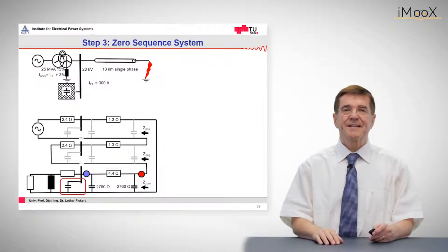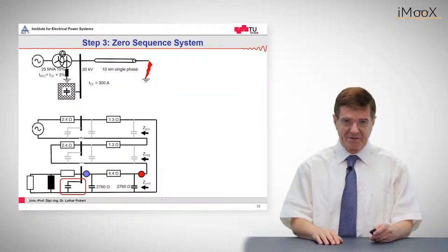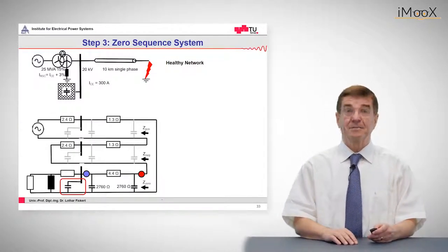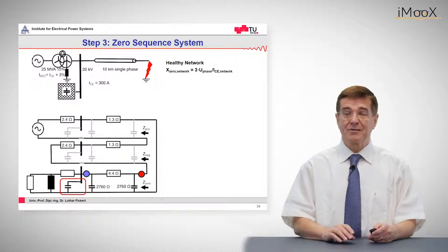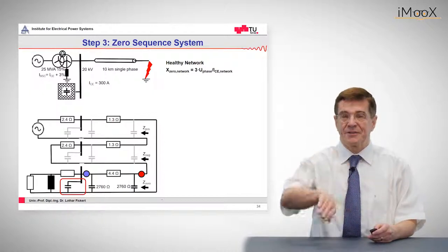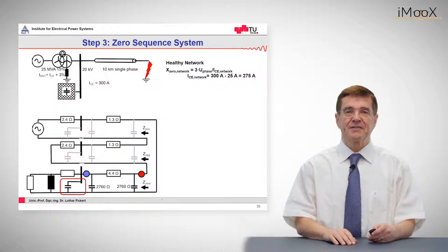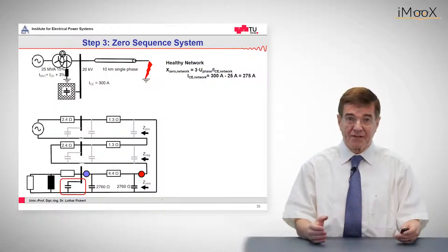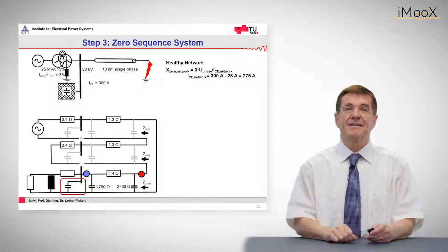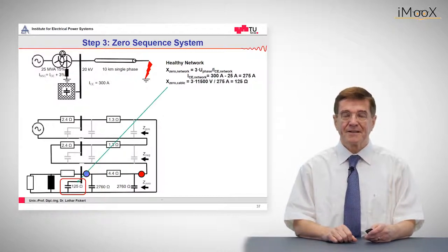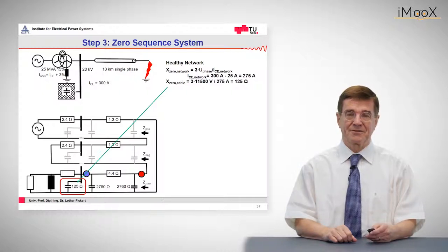So the next element is the healthy network, as we call it. The healthy network impedance is again a capacitive reactance, which is given by the well-known formula three times phase voltage divided by earth fault current. And in this case it is the difference of the total earth fault current minus the capacitive currents of the faulty cable. In this case it's 275 amps. And that finally leads us to a reactance of 125 ohms.